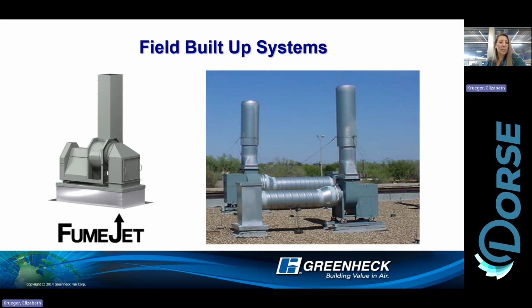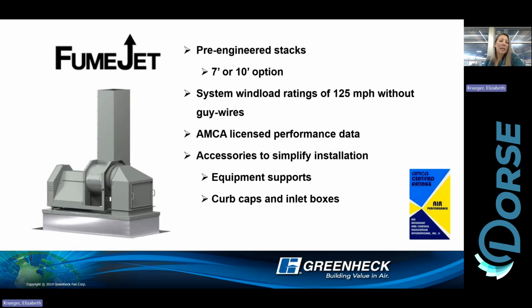What's really nice about these is you see the wires that are in that picture there. There are no guy wires on this. So, a very useful setup. Small footprint, and again, no need to run additional ductwork. You bring that duct right up to the fan. So here's the breakdown of that. Again, 125 mile per hour wind loads.